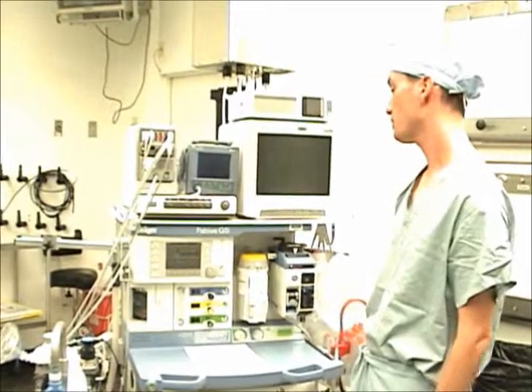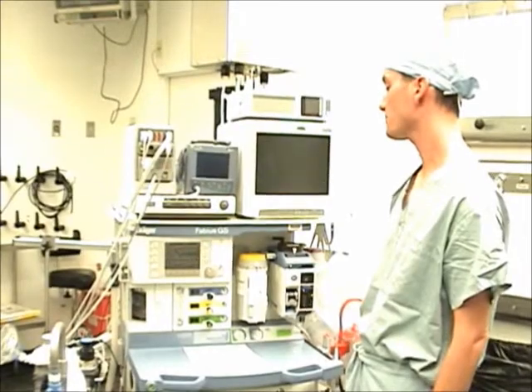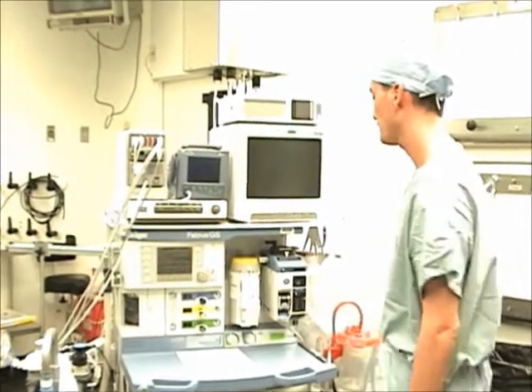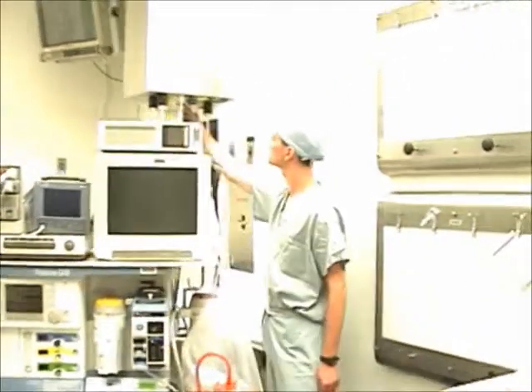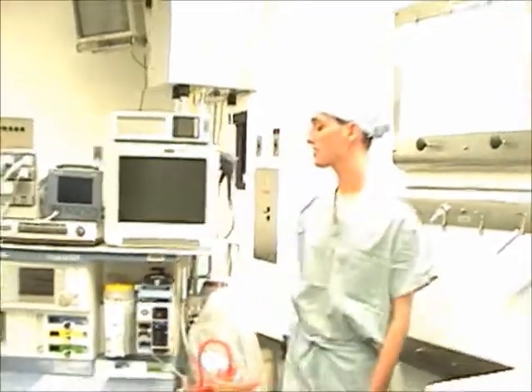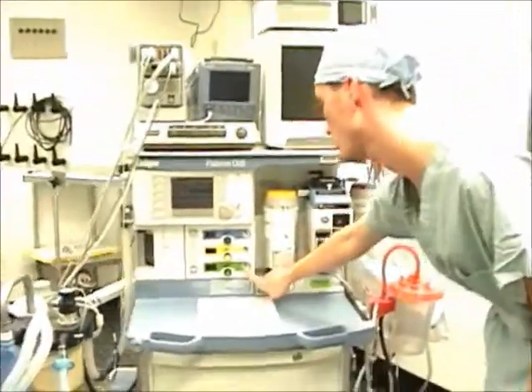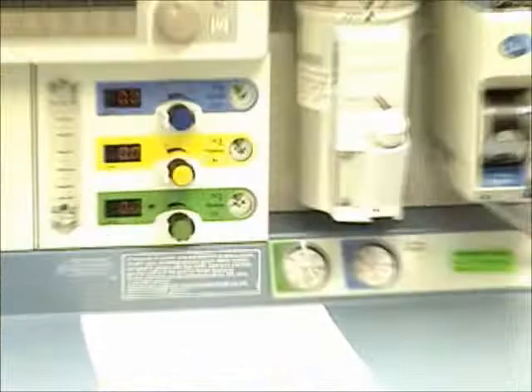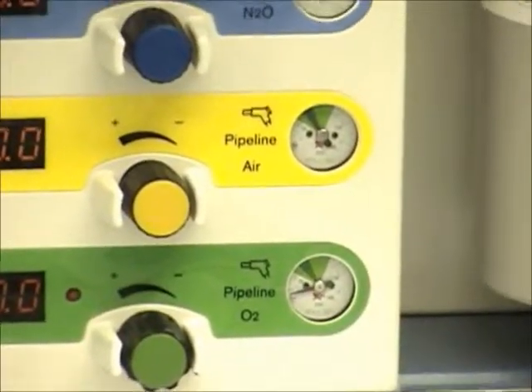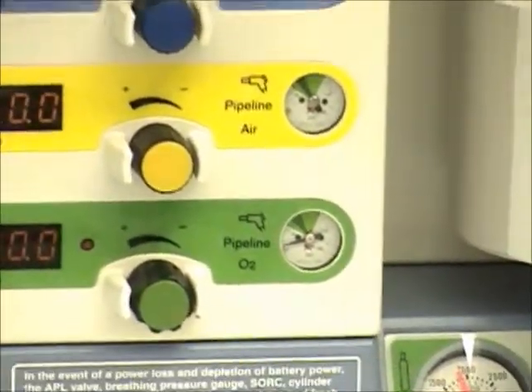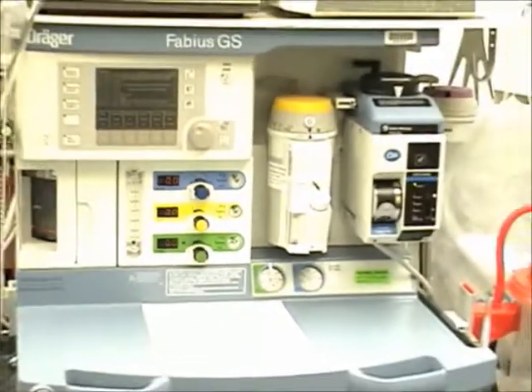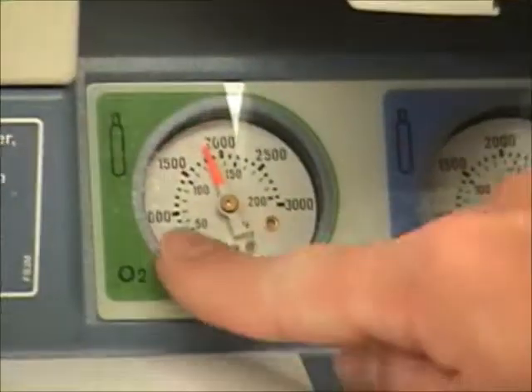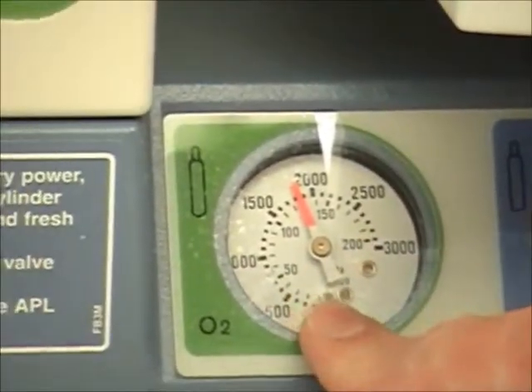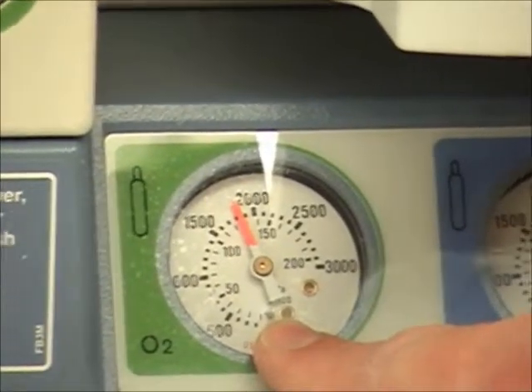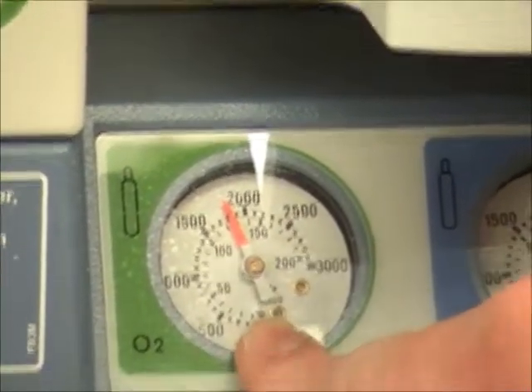Next, conduct a high-pressure system check. Disconnect the oxygen pipeline supply hose from the wall outlet. The oxygen pipeline supply gauge should now read 0. Open the reserve oxygen gas cylinder. Verify that the oxygen gas cylinder gauge reads at least 1,000 psi. We have approximately 1,800 psi here.